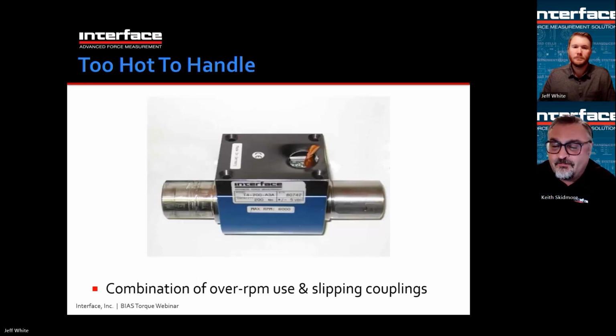Moving on. What happens as that shaft spins, or the hub spins on the shaft? This one got very, very hot. And you can see the aluminum housing actually got hot enough that it sagged down. So you can see where the connector used to be. That's actually bent down due to basically the cable weight and the extreme heat. Apparently this was glowing red hot.